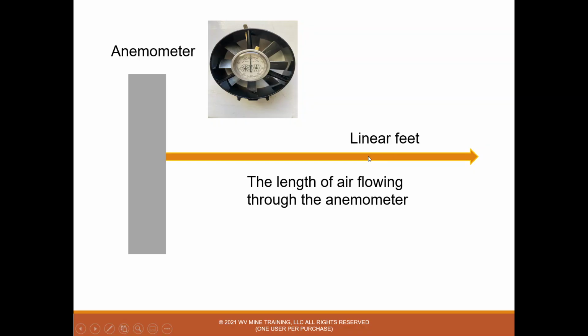If I stand in an entry with my anemometer and start it and let it run for 1 minute, then stop it and my reading is 500, that means the air that went through there in the first second is now 500 feet down the entry one minute later. So my air reading would be 500 linear feet per minute. That gives us 3 dimensions to calculate the cubic feet of air flowing down the entry: the width, the height, and the length.